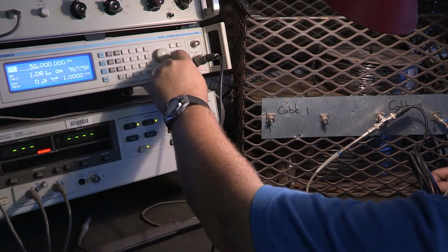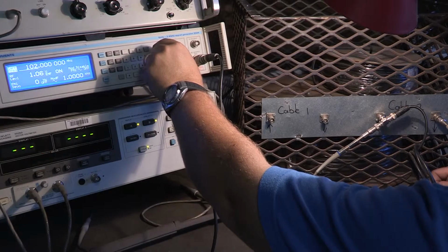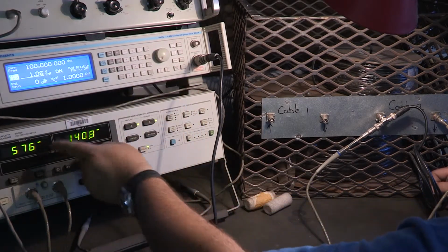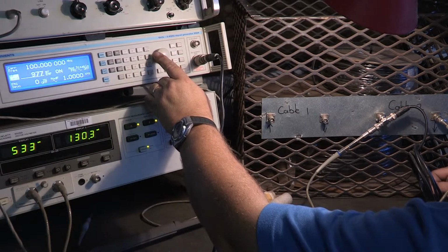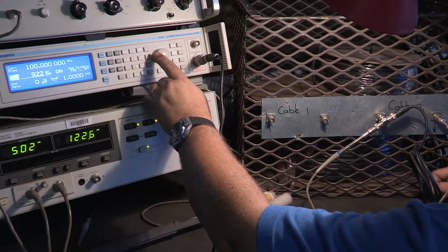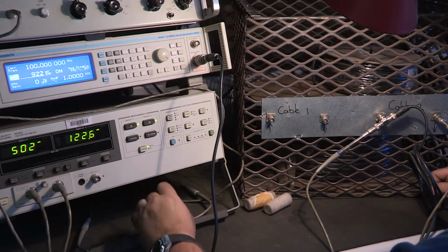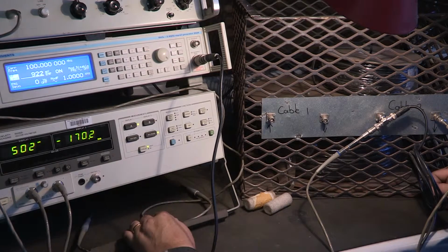So carrier, and we are just going for a 100 megahertz. The RF level, make sure that you are putting on channel A the same going into the cable, 500 millivolts, or as close as you can. This one is very finicky, but it works. That's close enough. And now I've got 122.6, and the phase angle minus 170.2.